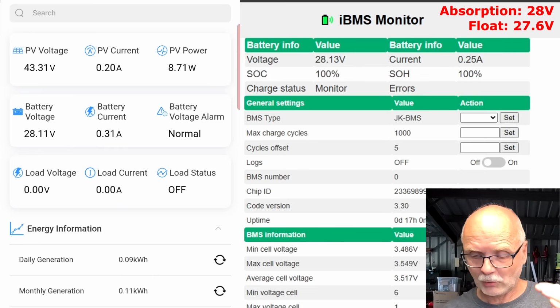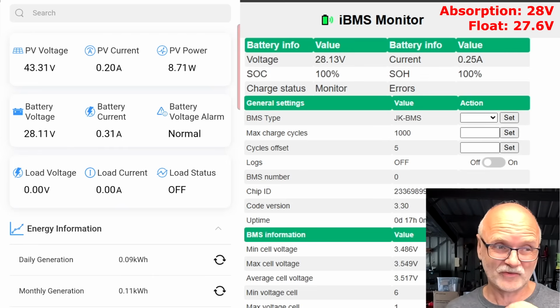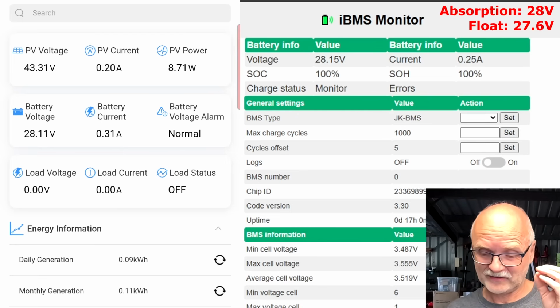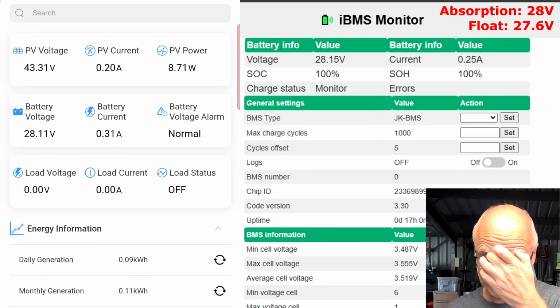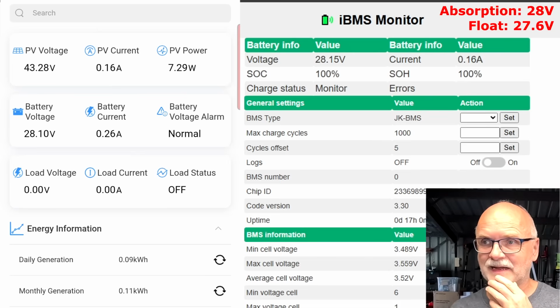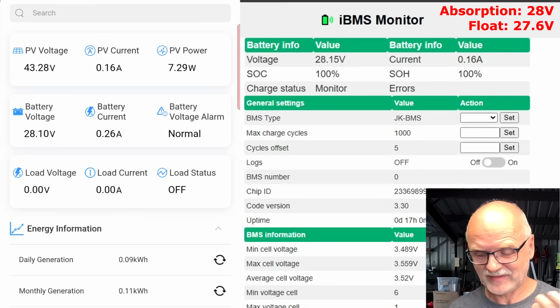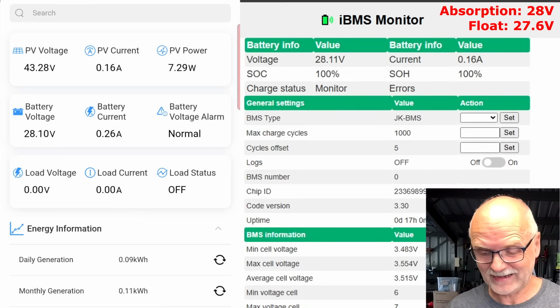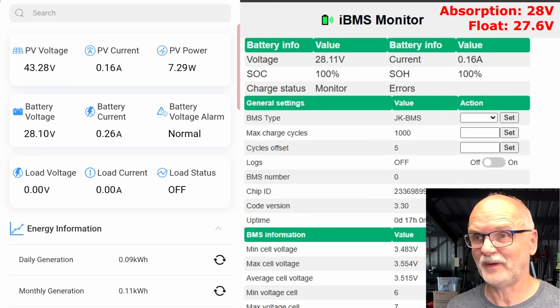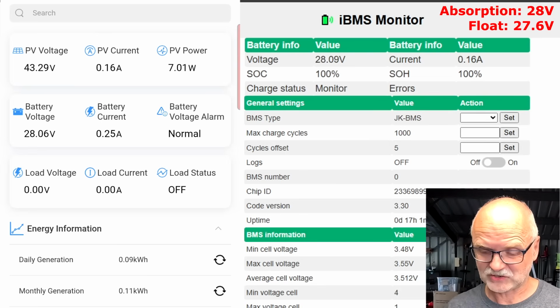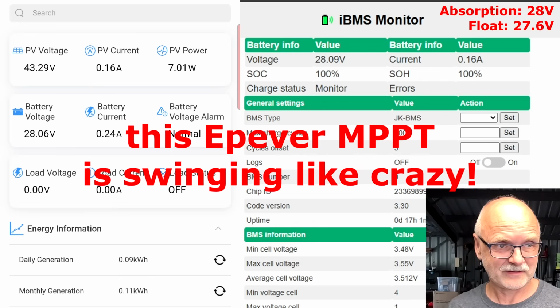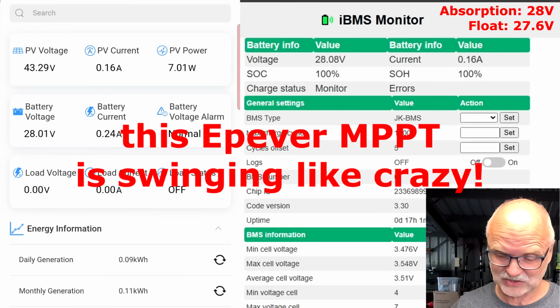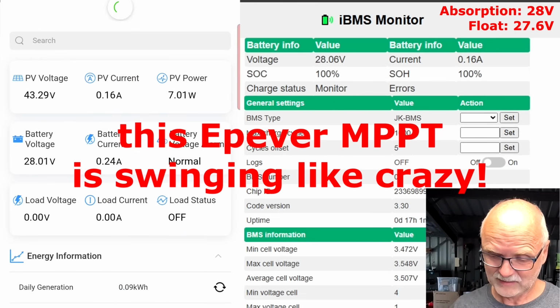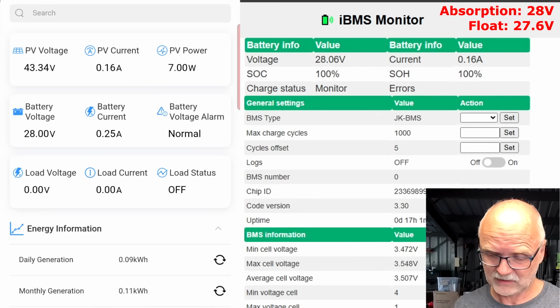It should actually hold the 28 volts now as good as possible, but it went up over 28.2 volts for whatever reason. 28.10 - I'm not too fussed about 0.10 of a volt, but even then, why? If we set 28, it should hold 28, not 28.1. Oh, now it goes down, 28.06. So is it still in bulk, or in boost, or in equalization, or is it going down to float now, because the voltage is going down?